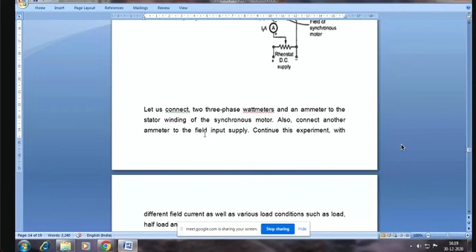this graph can be plotted at different load conditions. In this particular graph, we are doing it at no load. That means no load is connected to the synchronous motor. The motor is just run freely. And the field current is continuously varied. And for every value of the field current, the corresponding armature current is noted. Is it clear?